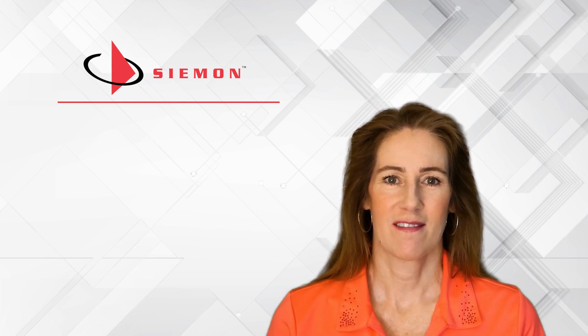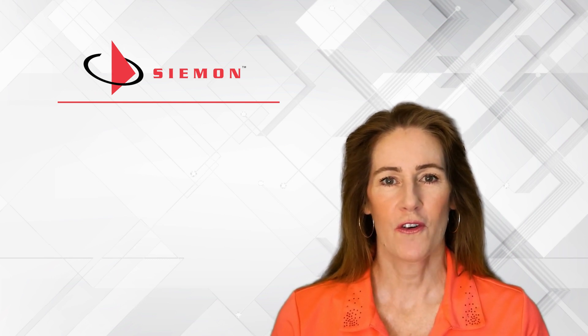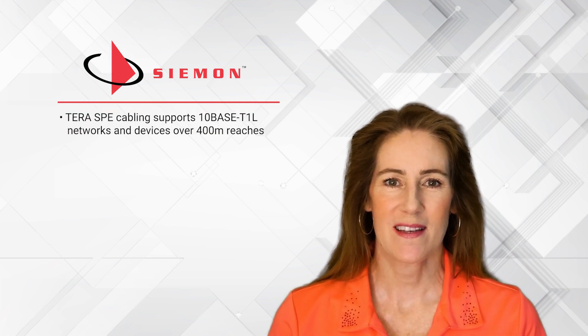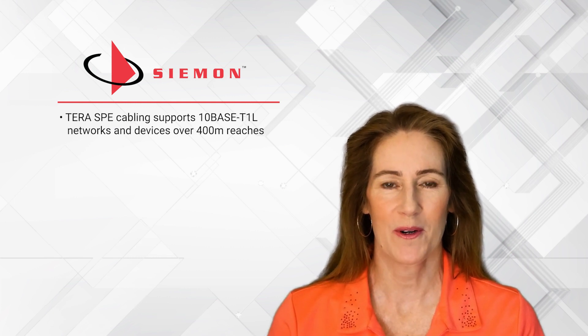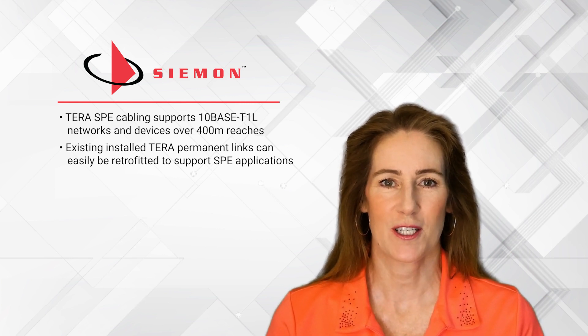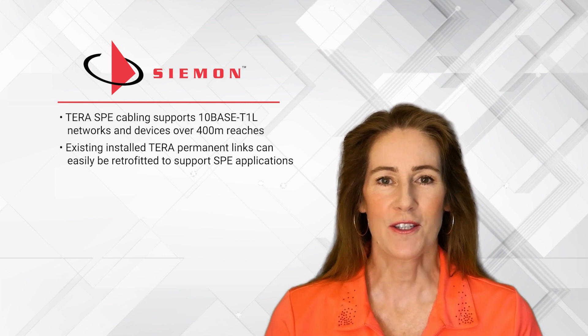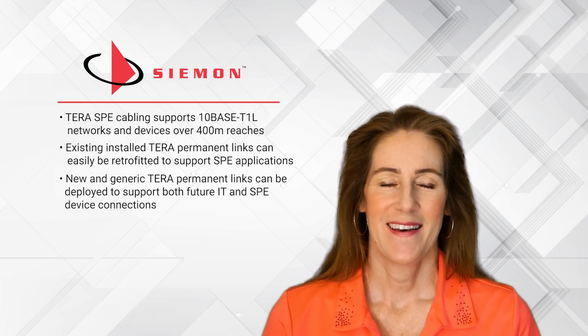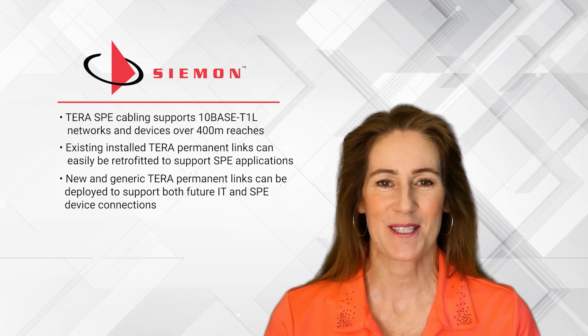This demonstration confirms successful transmission and operation of 10BaseT1L communications over a Siemon 400-meter SPE channel. The high performance and unique cable sharing ability of Siemon' Tera components means that existing installed Tera permanent links can easily be retrofitted to support SPE applications. It's also easy to specify new and generic Tera permanent links that are capable of supporting both future IT and SPE device connections using the four-connector expanded star channel topology. Thank you for tuning in to see Siemon' SPE cabling solution in action.